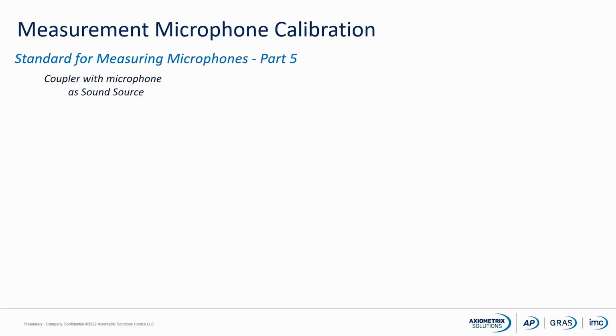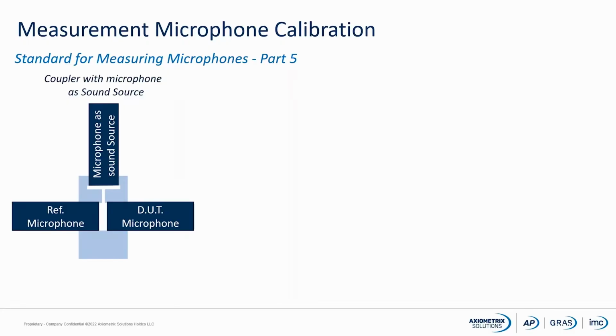If we have a closer look at the pistonphone and the calibrator, then we have a system like this. We can either use a microphone as a sound source, so the two microphones, the reference microphone and the microphone under test, will see exactly the same sound pressure levels. If we do it with a microphone as a sound source, then we are able to test or calibrate from about 20 Hertz to 20 kHz, and we will have levels around 100 dB in the little cavity, in the little volume we have between the two microphones under test.